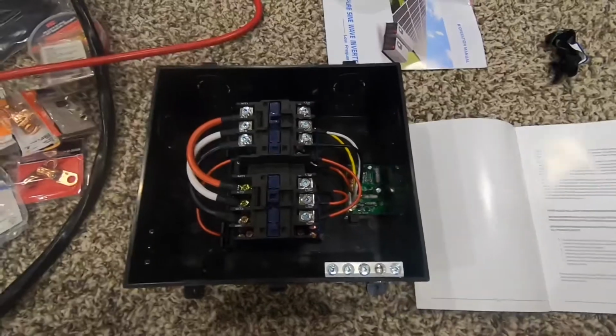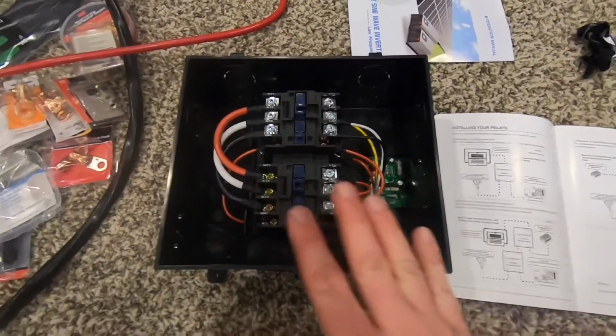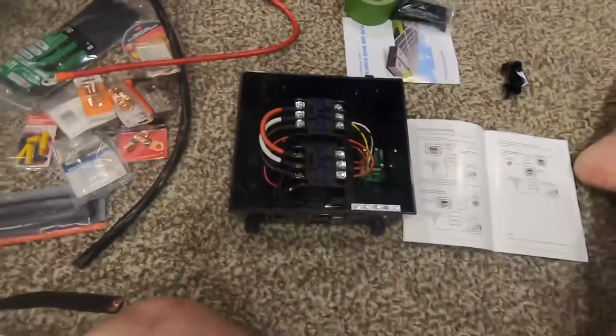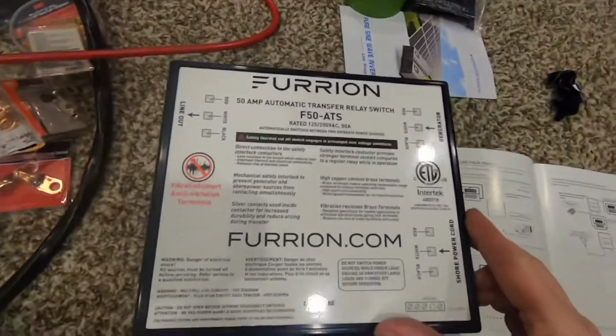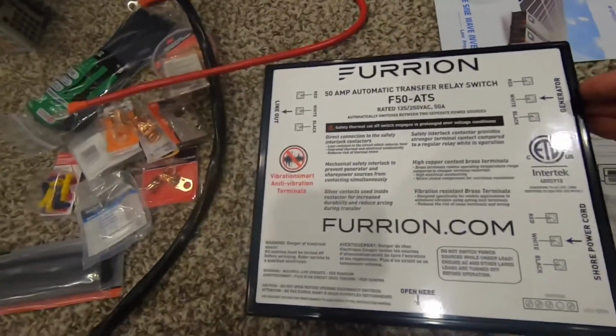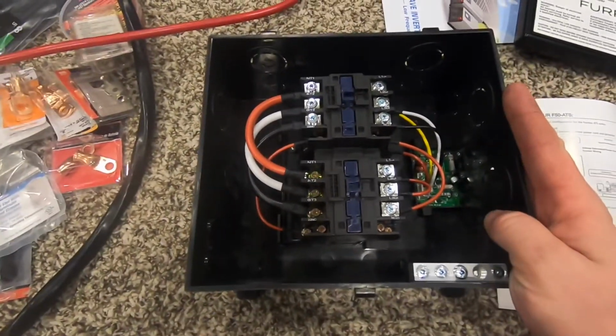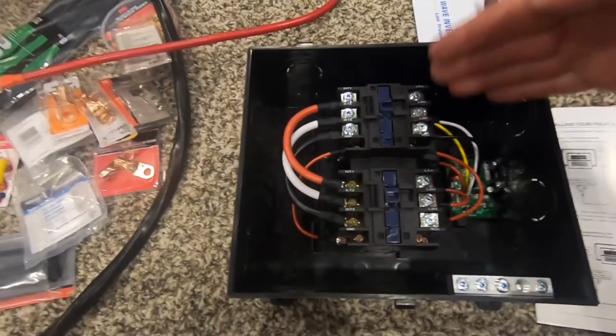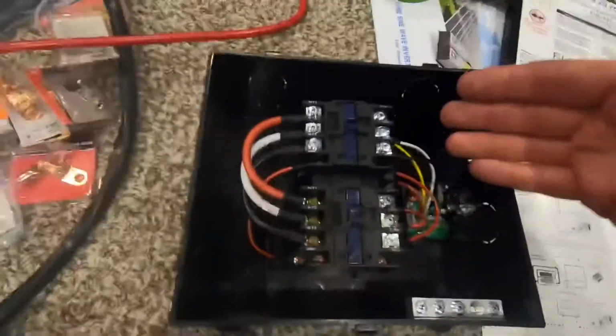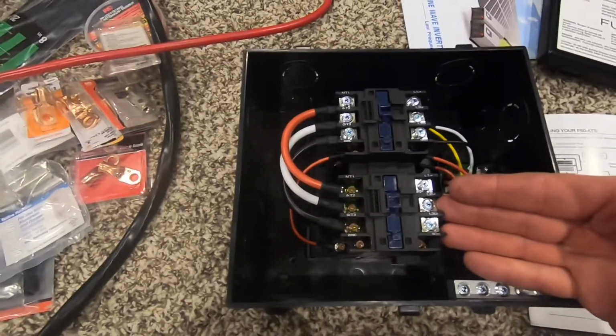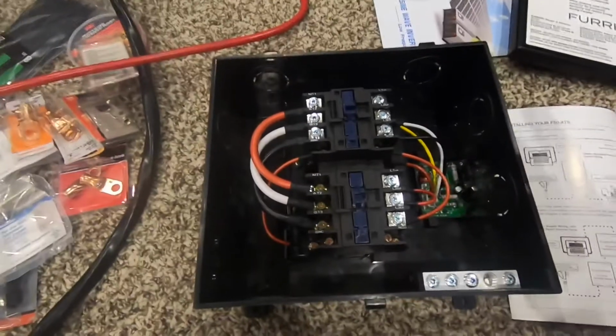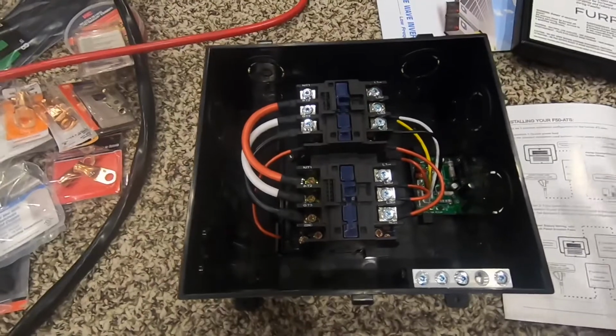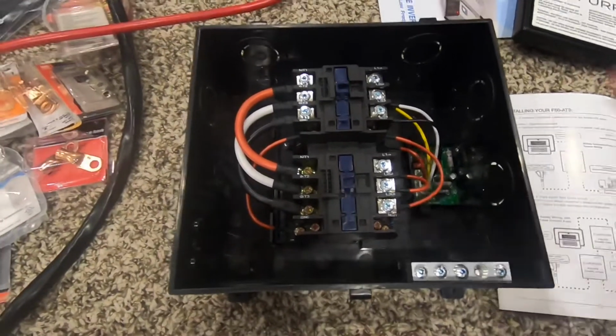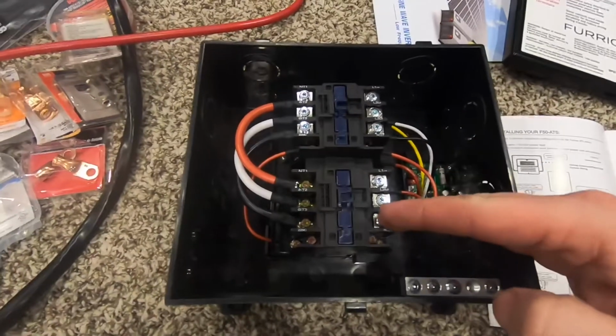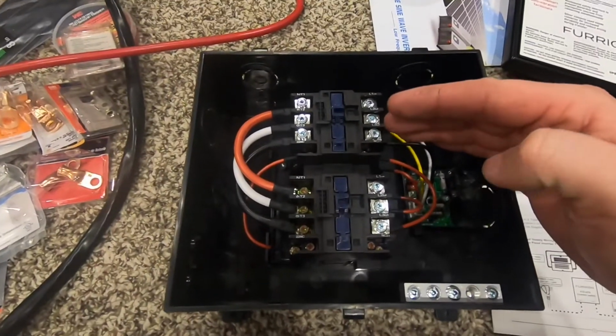The other thing I was looking at in the instruction booklet was how it would take priority. The transfer switch is wired so you get your shore power input on one side, generator input on the other, and then your line out. What it wants to do is take generator priority, and the generator is actually going to be the inverter, with shore power as secondary. So if I always have my inverter running and pull into an RV park connecting to 50 amp shore power, it's never going to switch over because it's always taking inverter priority, which isn't what I want.